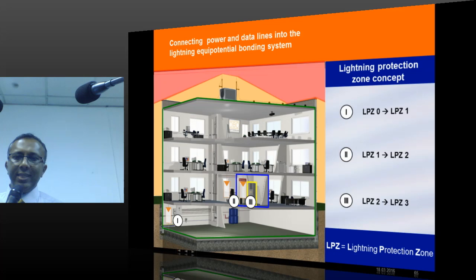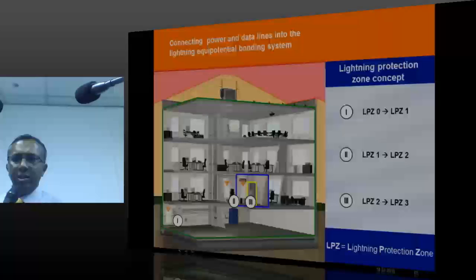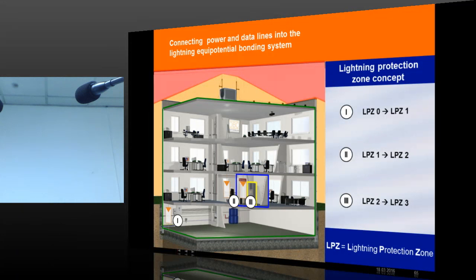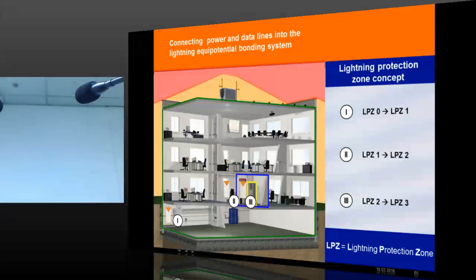So one example is what you see in this particular case here. LPZ0 and LPZ1, outside to inside, a wire which is coming from outside to inside. At this place you can have a spark gap, at the second place you can have a varistor, and at the third one you can have a diode. One example. It doesn't mean that this SPD is always a spark gap. No, an SPD can be any technology. The only thing is it has to satisfy the conditions explained in the standard. That's all.